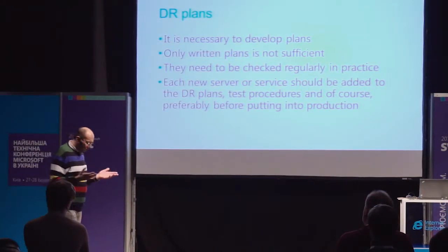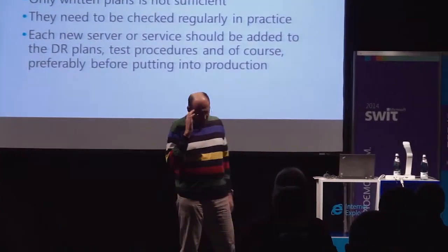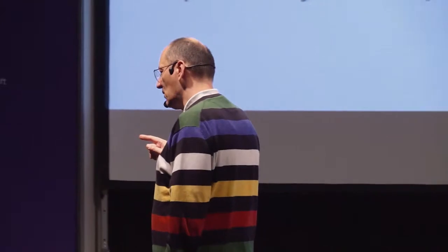So, stories like that. I have another funny story. One company had a diesel generator for electricity, but the diesel generator was put on the roof of a building, on the 5th floor. And they had a nice procedure to test this generator every week for 5 minutes. But people were lazy to carry diesel fuel up to the 5th floor. And once, when electricity really went out for a longer period of time than the batteries could handle, they designed batteries for some 20 minutes, the generator stood without fuel, and they had a disaster.